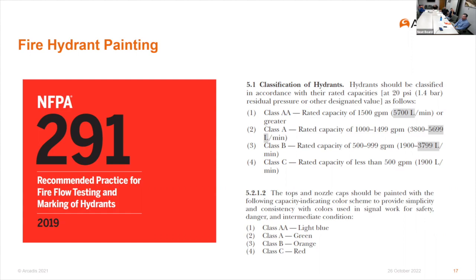So we have had water main breaks at the same time or after we've had firefighting incidents. So it is a concern for us. When you're moving that much water through the mains, typically you don't want to have the flow over 10 feet per second velocity, right? Thereabouts. When you're doing a fire flow test, you're going over that, so you're really stressing the system. You can cause problems, especially if it's not slowed down very, very slowly. You cause water hammer. So that's why we look at the locations where we're doing these things and plan it out very carefully.